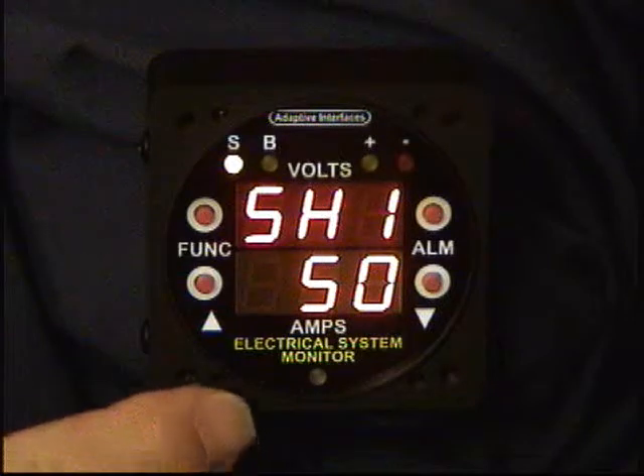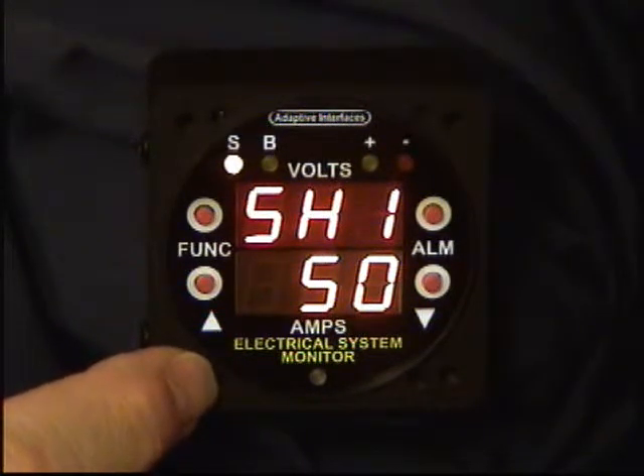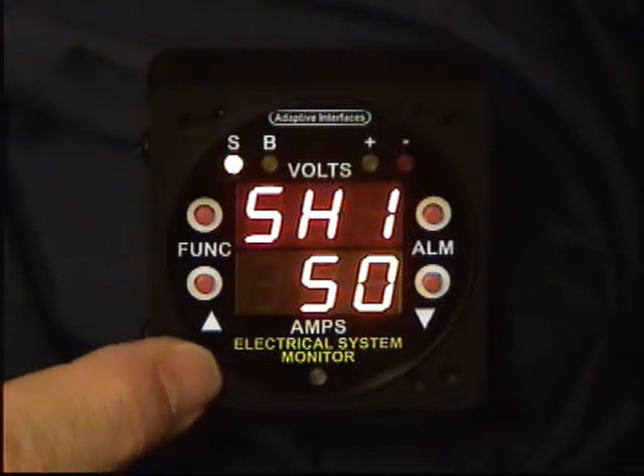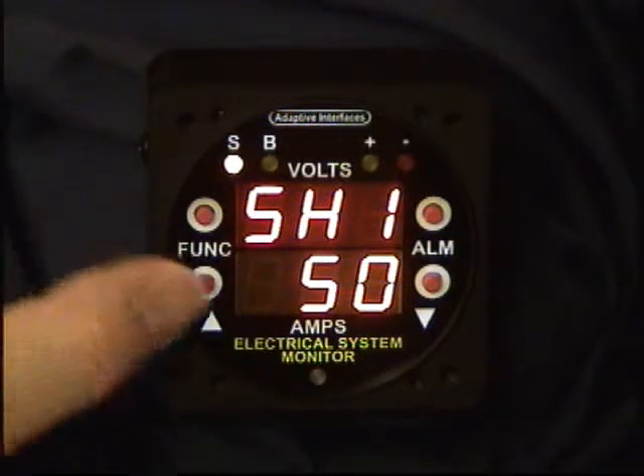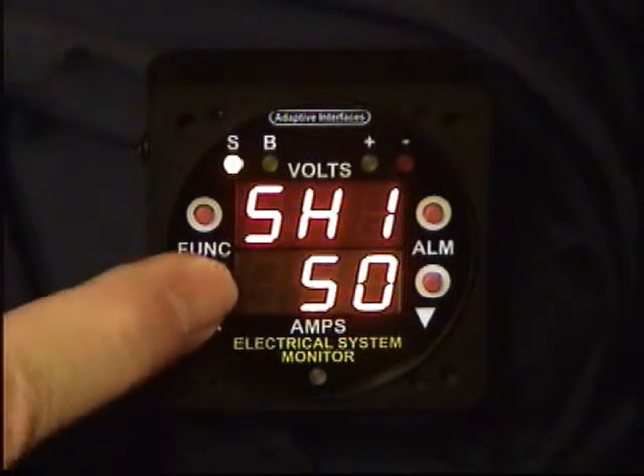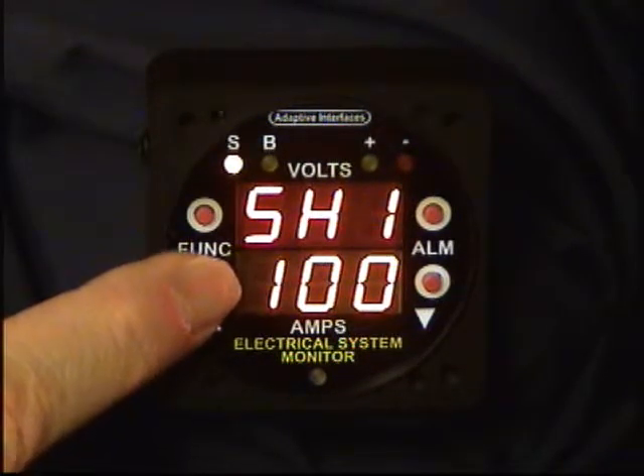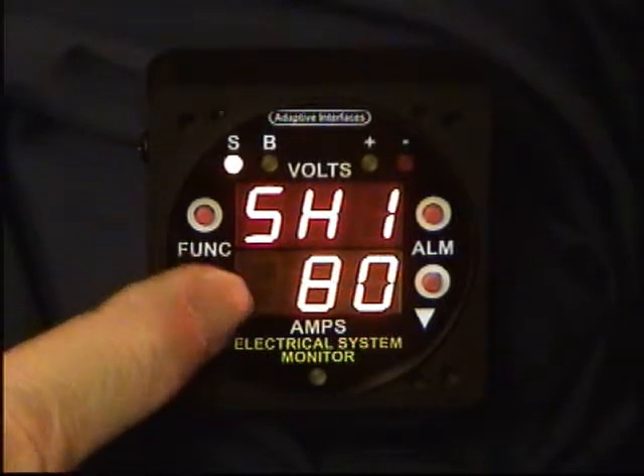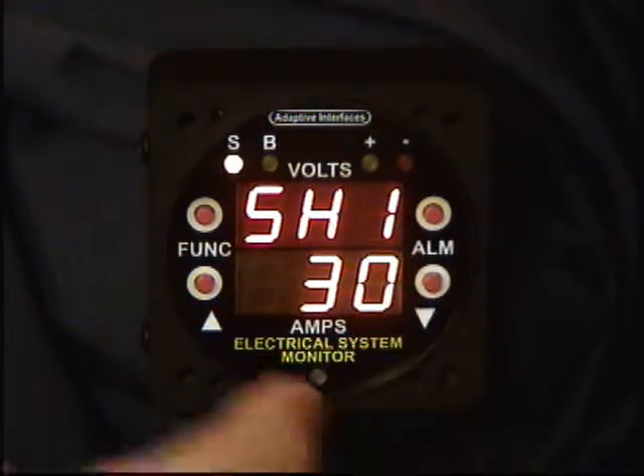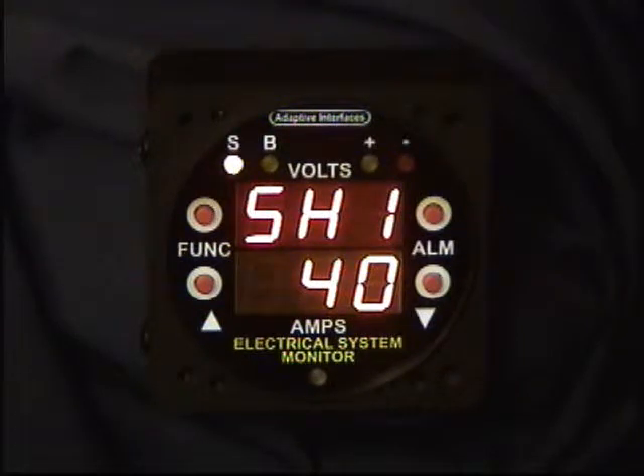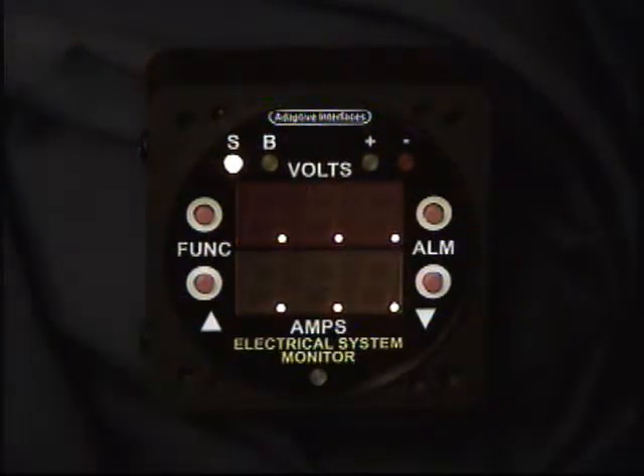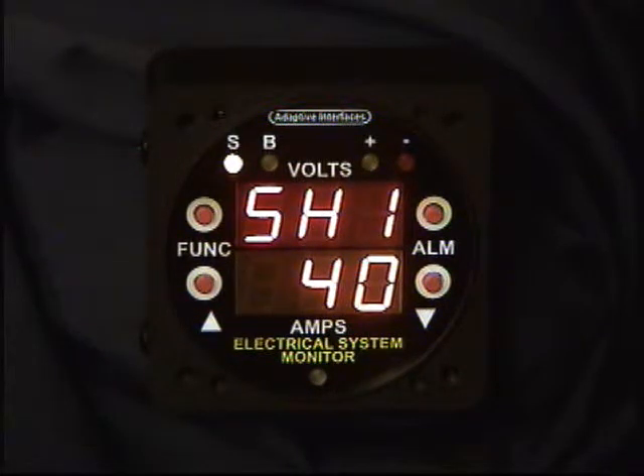The first function is the selection of the value of a shunt if a shunt is being used for current sensor 1 or the system current. Right now it's set for a 50 amp shunt. It can be selected anywhere from 10 amps to 100 amps, and you can do that by using the up-down arrows. Say we're using a 40 amp shunt. We can go ahead and select that by hitting the alarm, or in this case the enter button. Now the shunt is selected as a 40 amp shunt, so when 40 amps is going through the shunt it'll have a full value of 50 millivolts, and that's what the instrument measures.